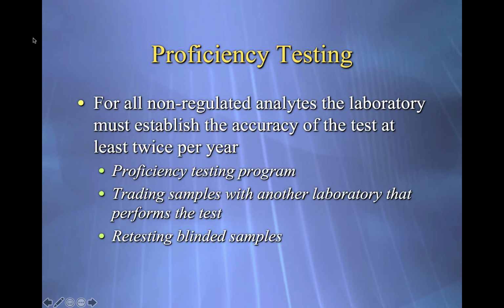If you're the only lab doing a particular test, you develop this wonderful new test and you're going to do a lot of them. Another way you could do this is to simply hold back samples that have been tested. Obviously hold them at a correct temperature, frozen or whatever, so they maintain their stability, and then feed them back through the system periodically as blinded samples and see if you get the same result. Document that and you've met this requirement.